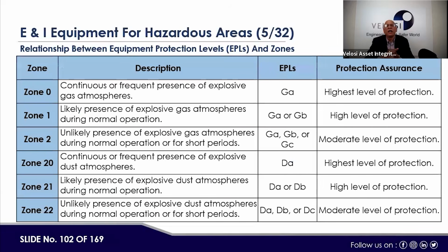Now here we see the relationship between equipment protection levels. What kind of protection is required for a normal equipment? We call it EPL, equipment protection level, for gas and for dust. For zone 0, zone 1, zone 2, then zone 20, zone 21, zone 22. These three I have added in this slide, but we did not explain earlier because we didn't cover the dust today, because in 2 hours we could not cover both.